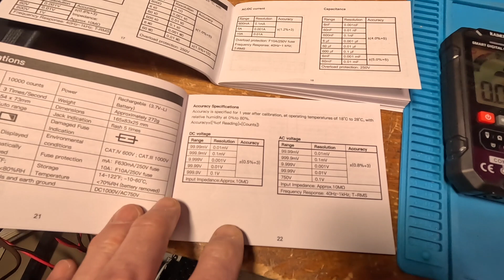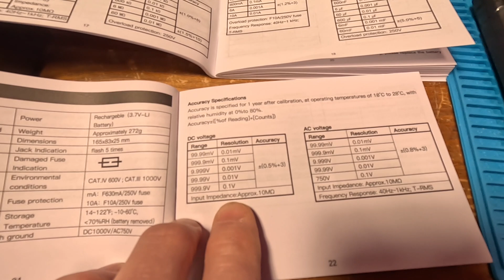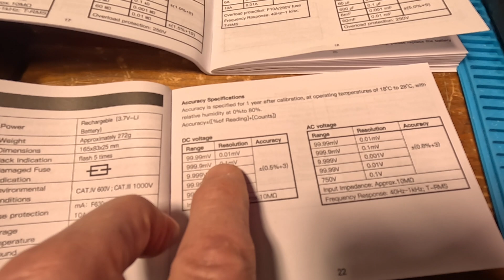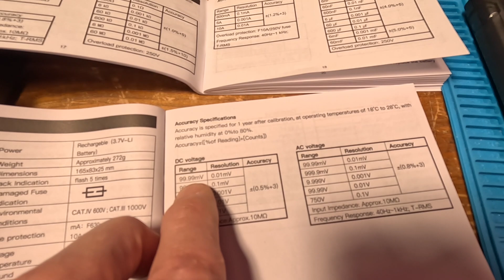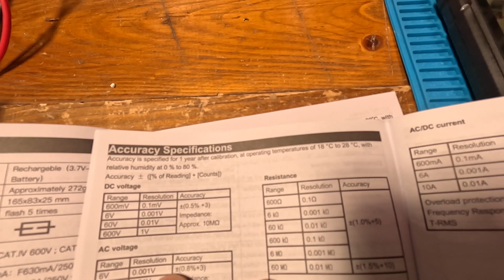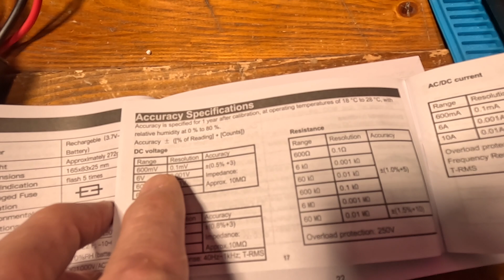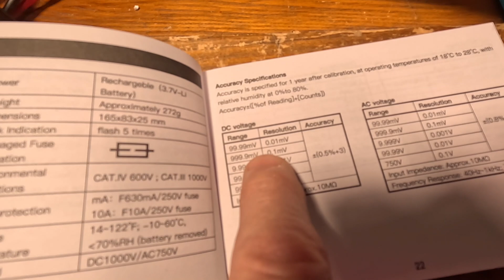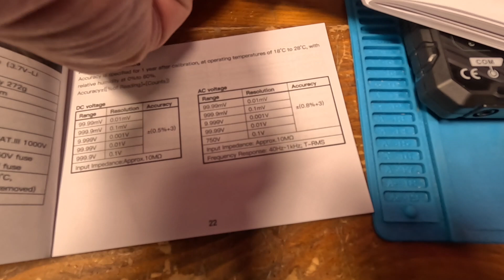So I had somebody try to tell me that I was getting accuracy and resolution mixed up just because high count meters are not more accurate, but they essentially are, because look at this. It's 0.5%, but 100 millivolts, you get 0.01 millivolts. On a 6,000 count meter, you still have the 0.5, but all the way up to 600 millivolts, you get 0.1 millivolt. So it's 10 times the resolution, and you only go up to 100 millivolts versus 600 millivolts.